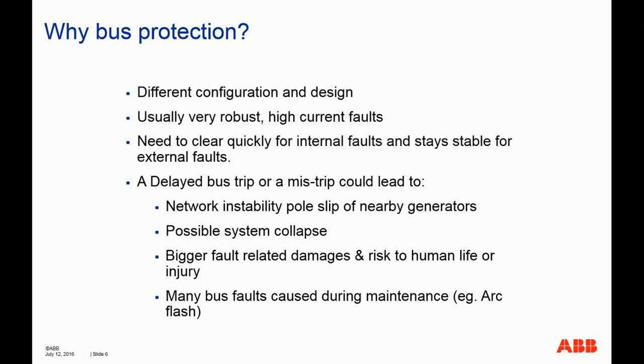Lots of feeders and lines tend to be connected to the buses. So if you misoperate the protections, you might inadvertently or unnecessarily take those loads off your system. Also, a delayed bus trip or mistrip could lead to network stability issues, for example pole slip. If the bus fault needs to be cleared sub-cycle, especially for high voltage buses near the generation plant, a delayed trip could cause pole slip or so-called out-of-step conditions that could destroy or damage the generators. It could also cause possible system collapse, and risk to human life.